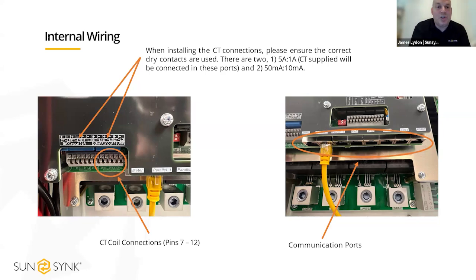So we wouldn't use the terminal strips on the left. And then the image on the right-hand side. At the moment, the yellow cable that's in there, that's a parallel lead. So if you've got multiple inverters connected in parallel, they've each got their own grid inputs. And the only thing on our side, essentially, that parallels them is the communication lead.